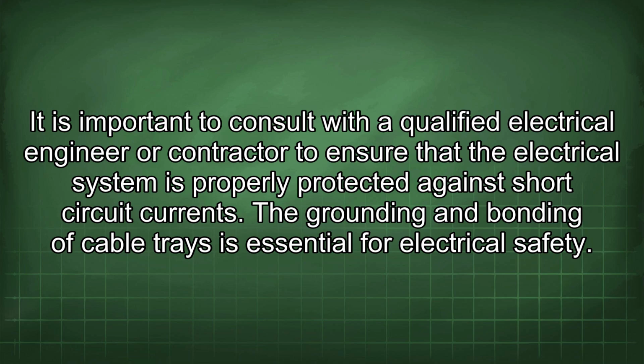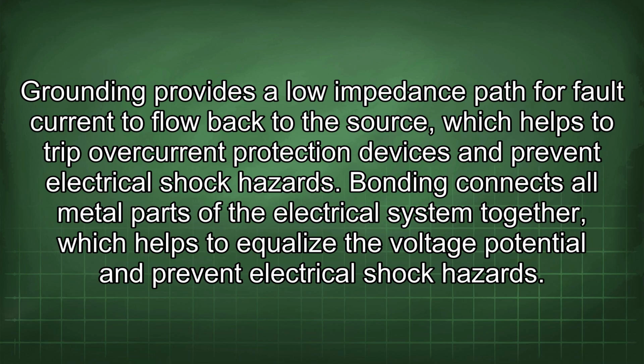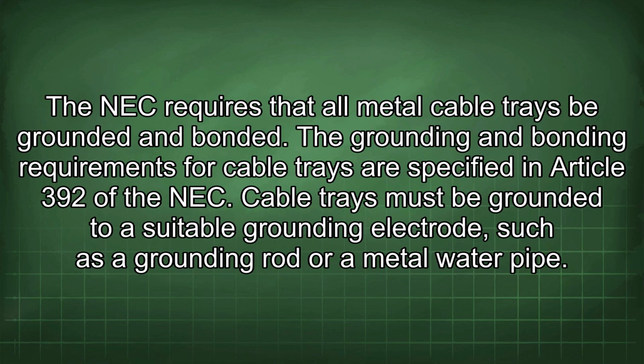The grounding and bonding of cable trays is essential for electrical safety. Grounding provides a low impedance path for fault current to flow back to the source, which helps to trip overcurrent protection devices and prevent electrical shock hazards. Bonding connects all metal parts of the electrical system together, which helps to equalize the voltage potential and prevent electrical shock hazards. The NEC requires that all metal cable trays be grounded and bonded. The grounding and bonding requirements for cable trays are specified in Article 392 of the NEC.